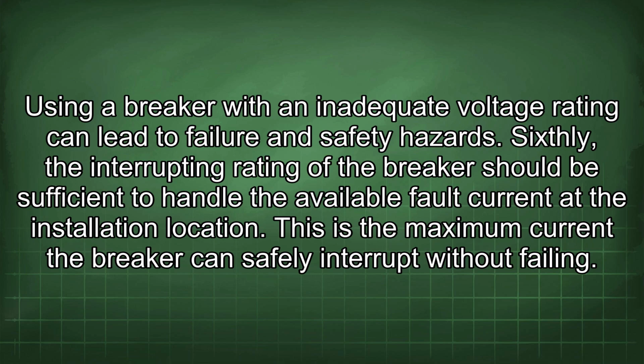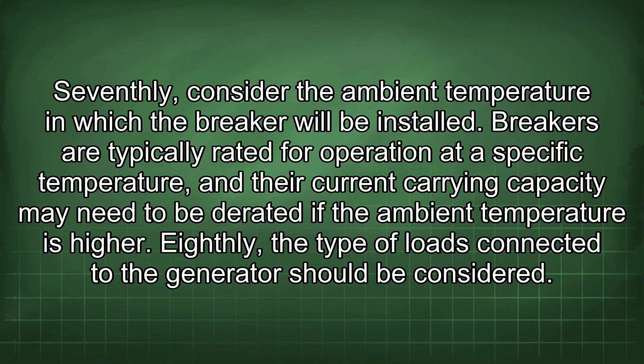Sixthly, the interrupting rating of the breaker should be sufficient to handle the available fault current at the installation location. This is the maximum current the breaker can safely interrupt without failing. Seventhly, consider the ambient temperature in which the breaker will be installed. Breakers are typically rated for operation at a specific temperature, and their current carrying capacity may need to be derated if the ambient temperature is higher.